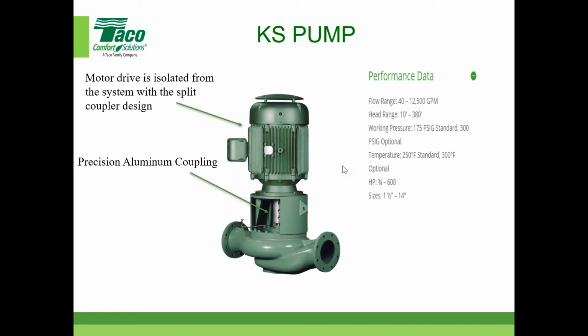As you can see on the right-hand side in the performance data, these KS pumps get up pretty big. Flow ranges start relatively small, but they go up to well over 10,000 GPM, with a pretty good size head range as you can imagine. The standard working pressure is 175, which covers about 80-90% of the business out there. But if it's a real high rise or something like that, you might want to up it to 300 psi, which is an option.